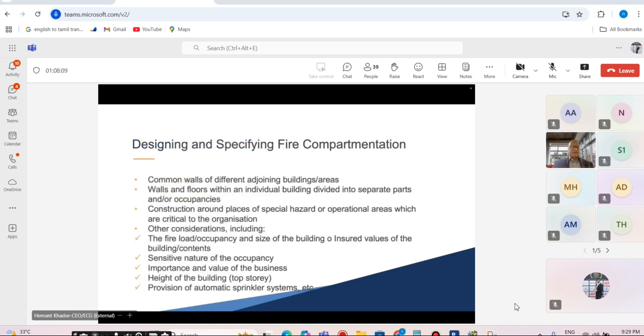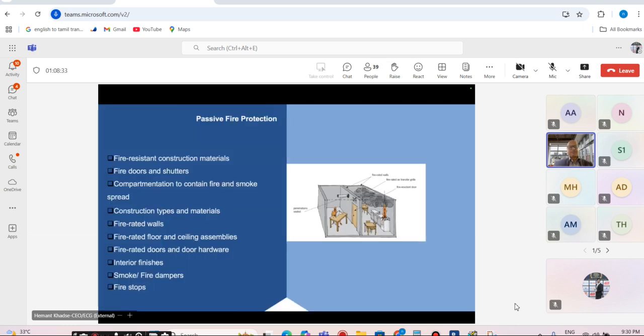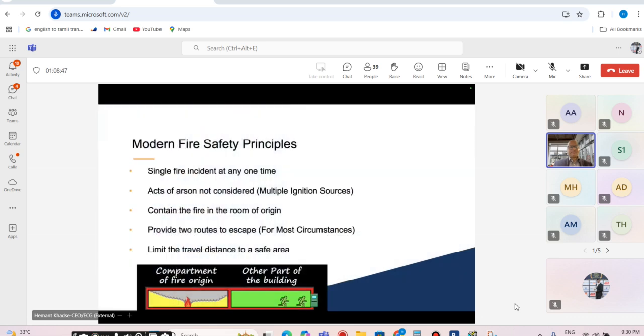It is important that you work with an architect to look at the fire barriers and the openings that are available, and again, based on the occupancy, you can decide what's my compartmentation requirement and how it can be achieved as a part of the passive fire protection strategy. So apart from the compartmentation, it is also important that your fire doors, walls, interior finishes, dampers, and fire stops are also well captured and defined very clearly.